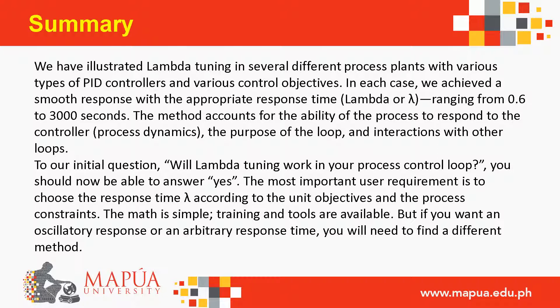Lambda tuning has been illustrated in several different process plants with various types of PID controllers and control objectives. In each case a smooth response was achieved with the appropriate response time lambda, ranging from 0.6 to 3000 seconds. The method accounts for the process's ability to respond, the purpose of the loop, and interactions with other loops. To the question 'will lambda tuning work in your process?' — the answer is yes, provided you choose the response time according to unit objectives and process constraints. If you want an oscillatory or arbitrary response time, a different method is needed.